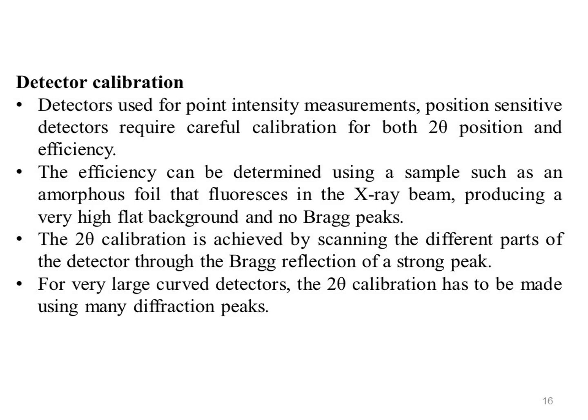For each channel, an exact 2 theta position is required together with an efficiency coefficient. The efficiency can be determined using a sample such as an amorphous foil that fluoresces in the X-ray beam.